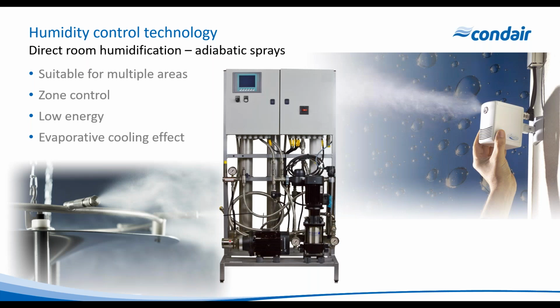You can use adiabatic systems as well. Here you can see a spray system that's utilizing a small spray head that can be attached to a local sensor and control valve, so we can have local individual control for many different zones running off a central water treatment and pump set. And you can have multiple zones, so if you've got different temperatures or different materials, you can run that humidifier to work in sometimes 15, 16 different zones. And of course, they're low energy because you're utilizing the heat energy in the air, in the space, and very often we've got waste energy from lighting and heating and solar gains, etc. So we can use that to offset the energy running cost of the humidifier system.